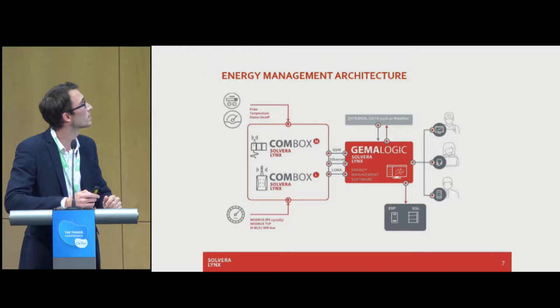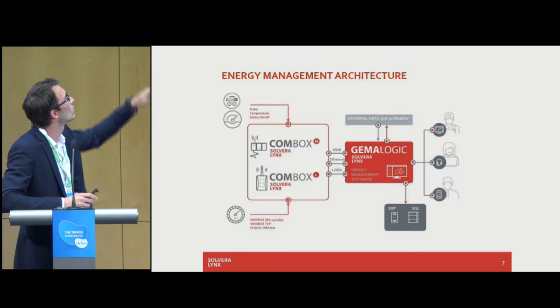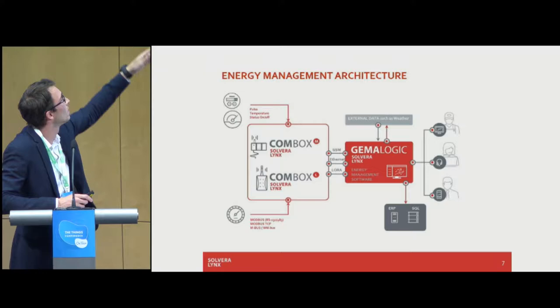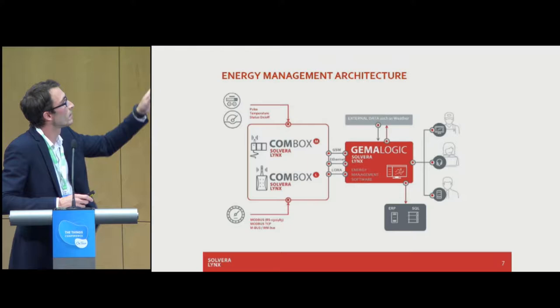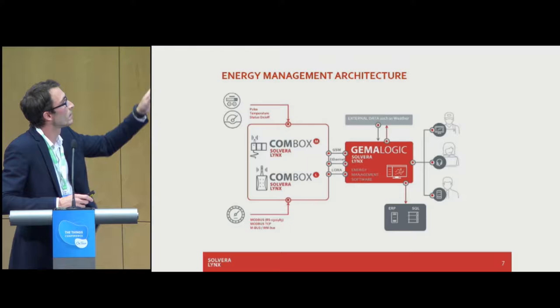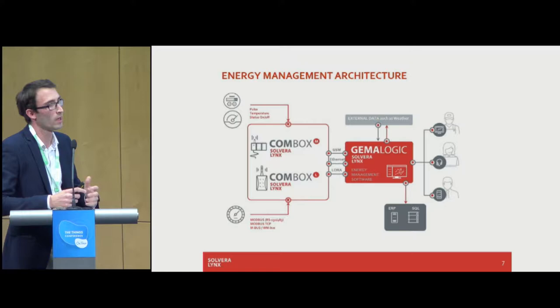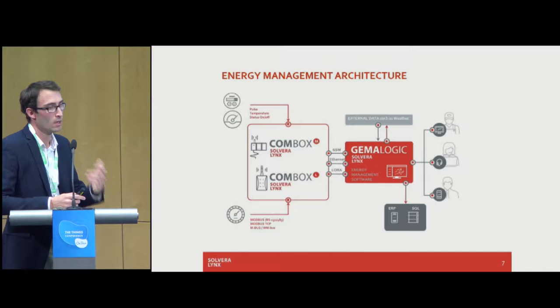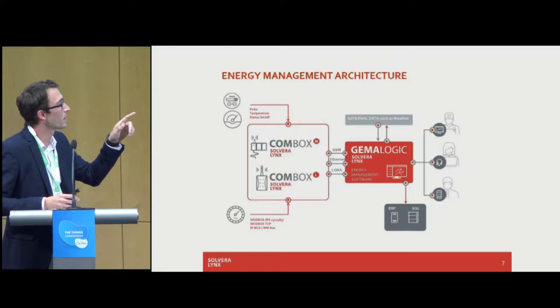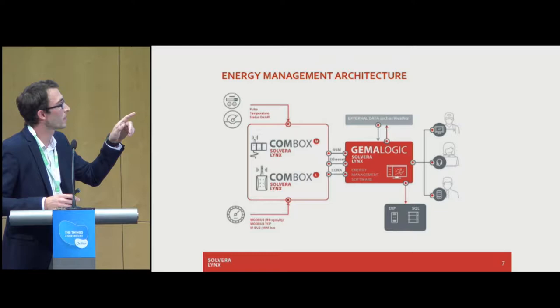The ComBox architecture supports different inputs: Modbus, Modbus TCP, M-Bus, pulse, temperature, and status on/off sensors, using different technologies — today focusing on LoRaWAN — through different protocols to GemaLogic. Since we're talking about energy management, we always take into consideration external data and weather conditions as well, especially when doing temperature monitoring. Another option of GemaLogic is integration with ERP systems or external databases, and every user can analyze their own data, building their own reports and dashboards.